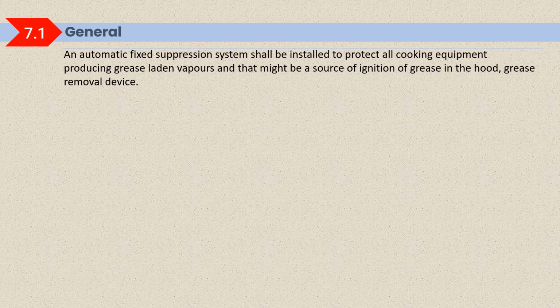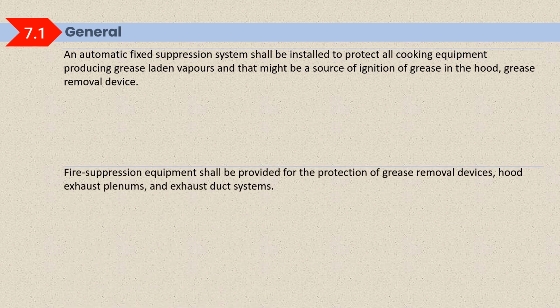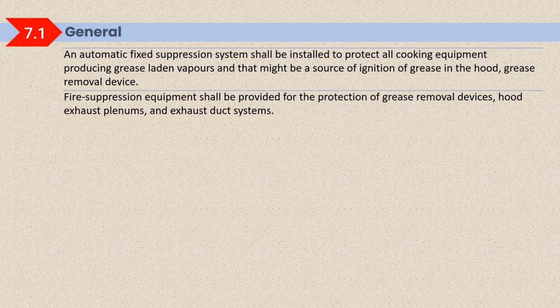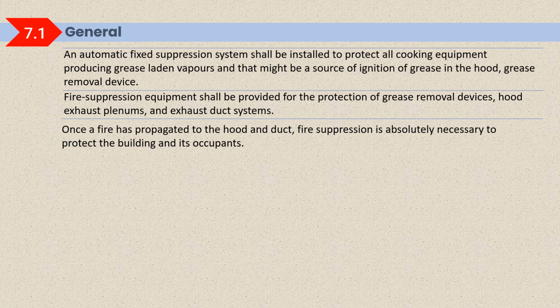An automatic fixed suppression system shall be installed to protect all cooking equipment producing grease-laden vapor that might be a source of ignition of grease in the hood grease removal device. Fire suppression equipment shall be provided for the protection of the grease removal device, hood exhaust plenum and exhaust duct system. So you can see it is not required only for protection of the grease removal device. It is also protecting the hood, exhaust plenum and exhaust duct system. Once a fire has propagated to the hood and duct, fire suppression is absolutely necessary to protect the building and its occupants.